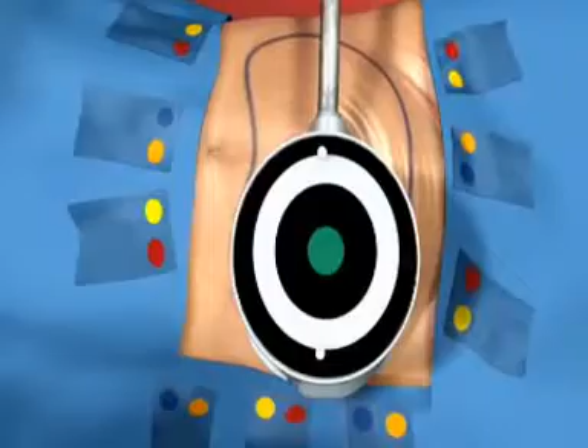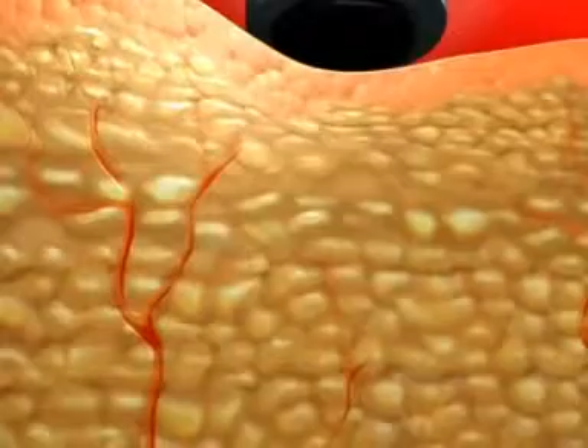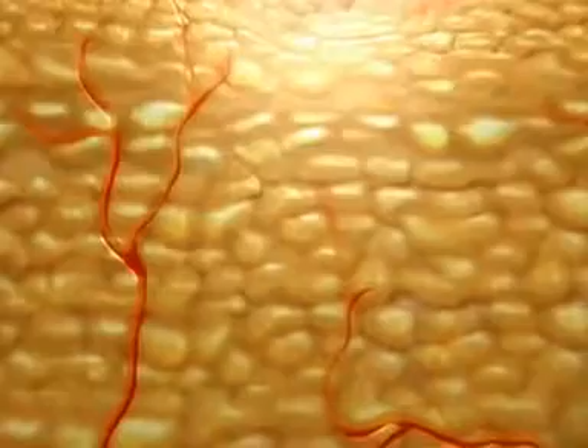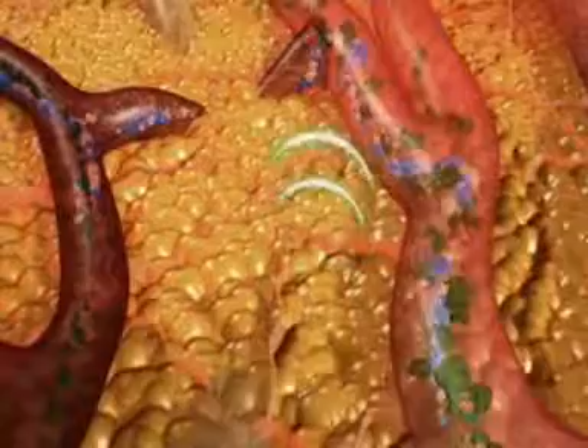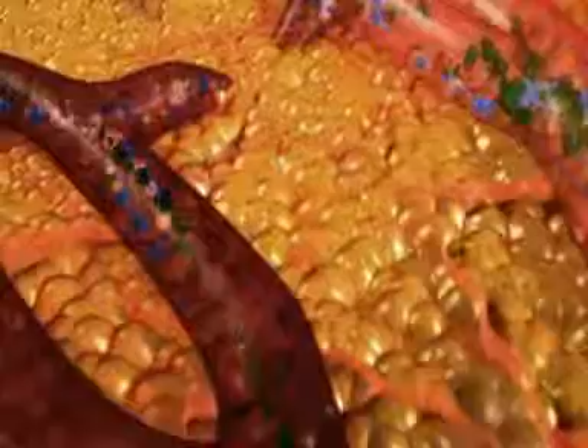The transducer delivers an ultrasonic beam and provides real-time acoustic and optical feedback on treatment. It uses multi-directional acoustic waves to ensure that focused energy is applied to the selected area only. Specific ultrasound parameters of pulse length and energy level ensure selective damage to fat cells only. Non-adipose tissue, not being susceptible to these parameters, remains undamaged.